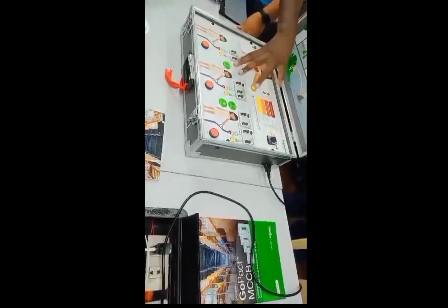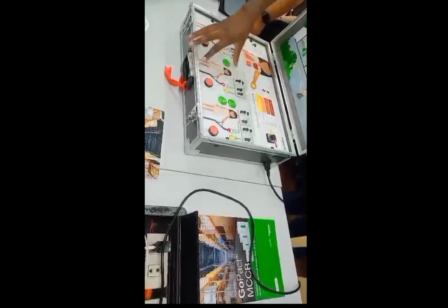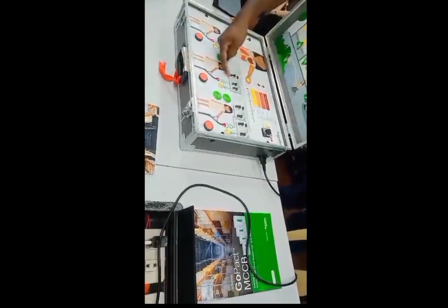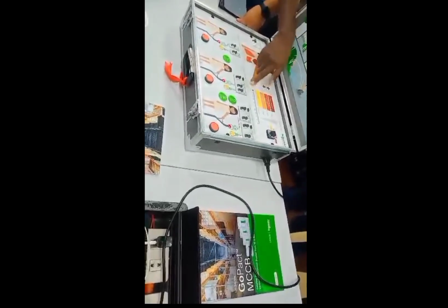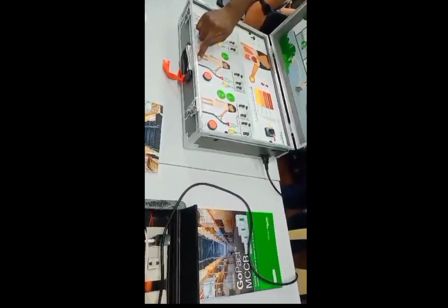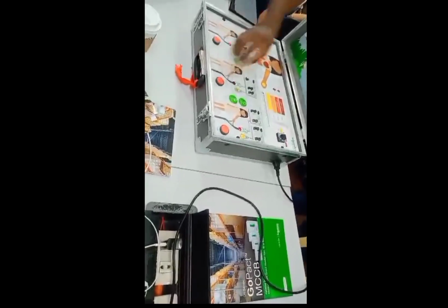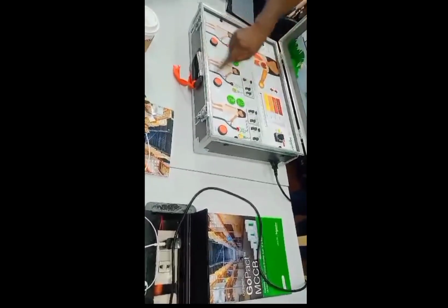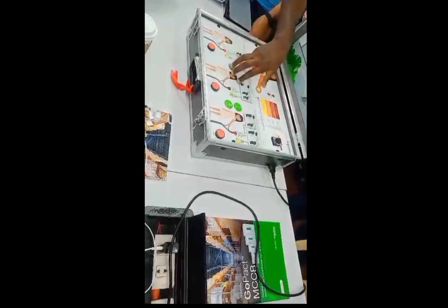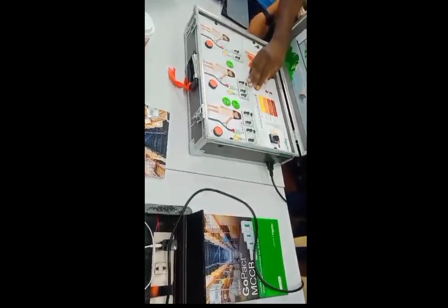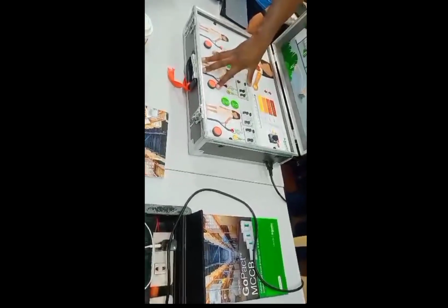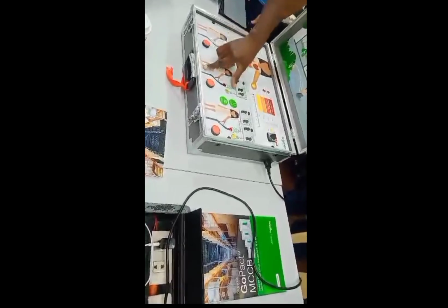Now here, you have the first scenario where you have one RCCB protecting the whole installation. So the wiring here is main power. Then this RCCB is supplying both MCBs. So this is like the main incomer. Now here you see that the fault will simulate is only on the socket line. So when I simulate it, because the main incomer trips, both the socket line and the light line is powered out. So the person is still protected, so this is okay for people protection because you can come back and switch it on and you continue to have power. It's okay for people protection, but it's not very good for continuity because the lights have now been switched off, but the fault was on this other side.